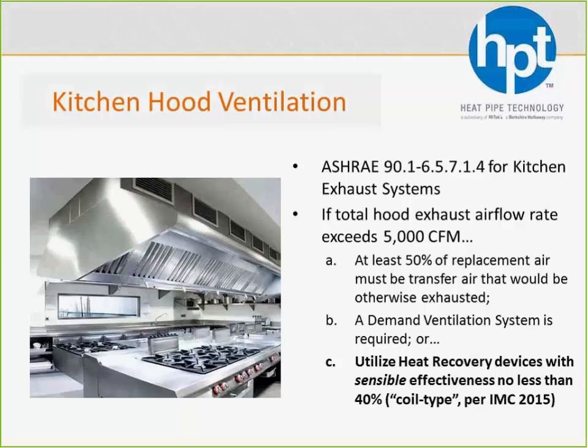You can do a demand ventilation type system, a little beefier control setup, or you could use a heat recovery device that ASHRAE says has to be a sensible device, and per the IMC, it has to be a coil type device because they recognize that air is going to be grease laden, and it's a lot different getting that out of other devices than it is something like a heat pipe where it's a lot easier to clean. And the minimal effectiveness is 40%, which is a piece of cake for a heat pipe. So if you have any kitchen exhaust systems and they have to meet code, use that heat pipe.